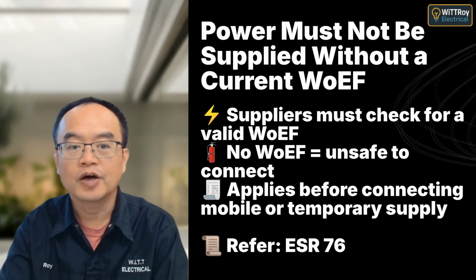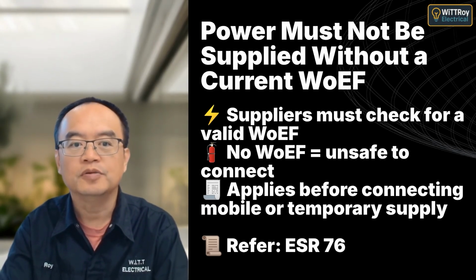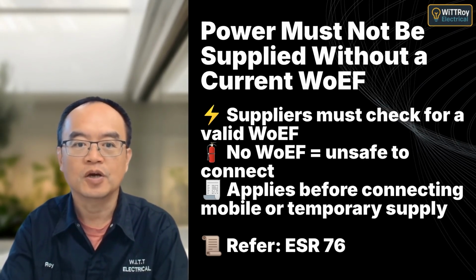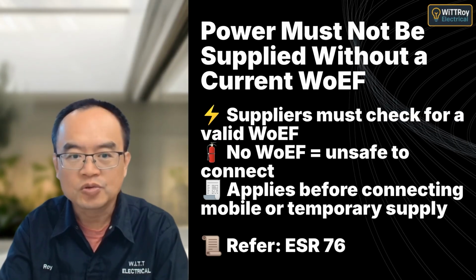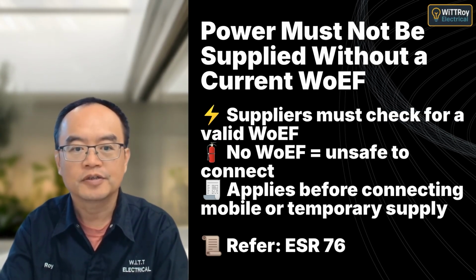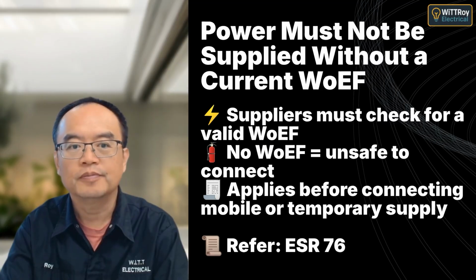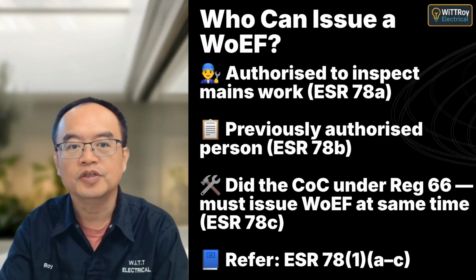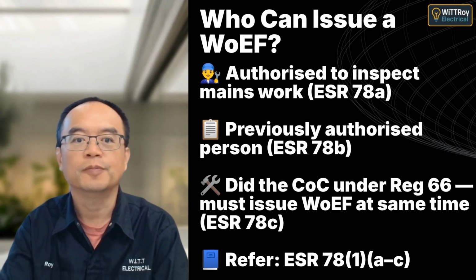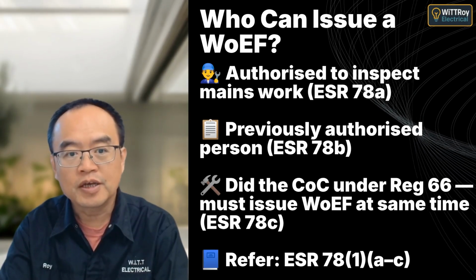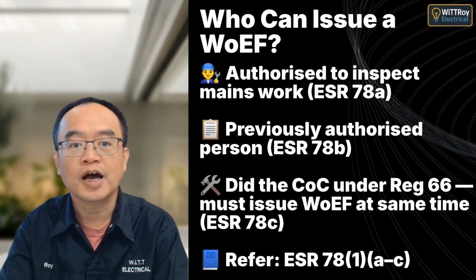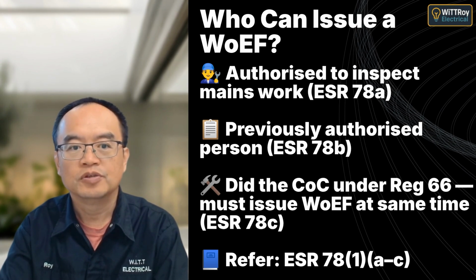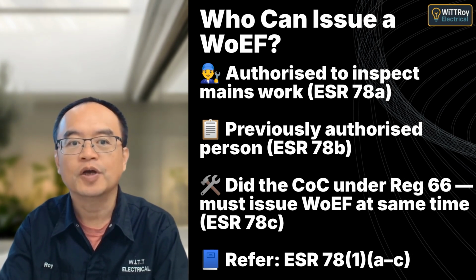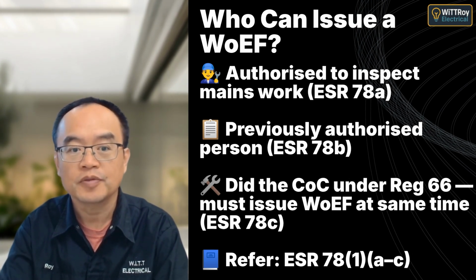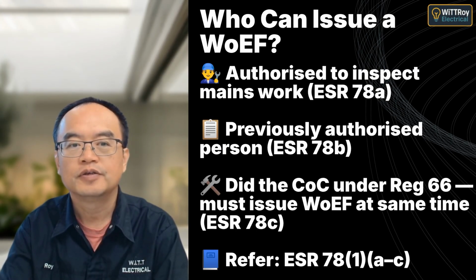Before connecting any power to a connectable installation, the person supplying electricity must confirm that a current WOEF is in place. This ensures the installation is safe before it's energized. A WOEF can only be issued by someone authorized to inspect mains work, someone previously approved by the secretary for the same class, or the person who issued the COC under Regulation 66, but only if they issue it at the same time. A licensed electrician cannot issue a WOEF unless they meet one of these conditions.